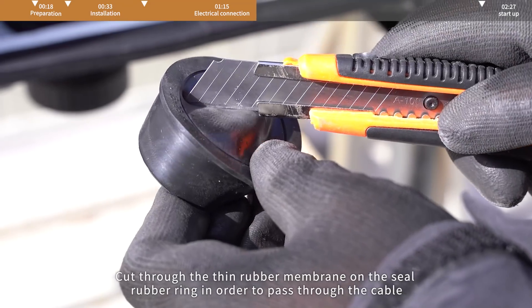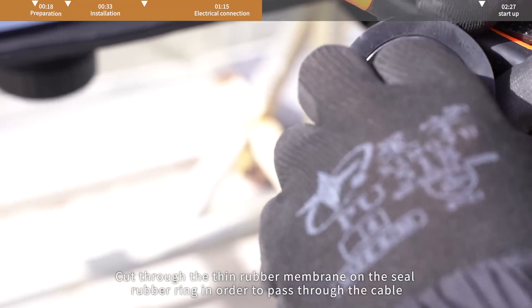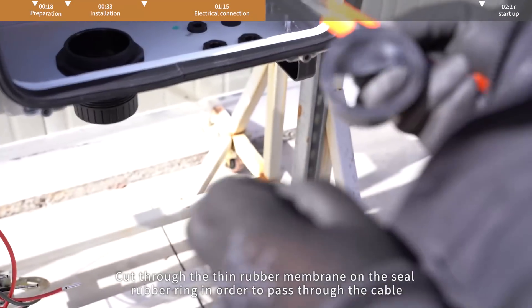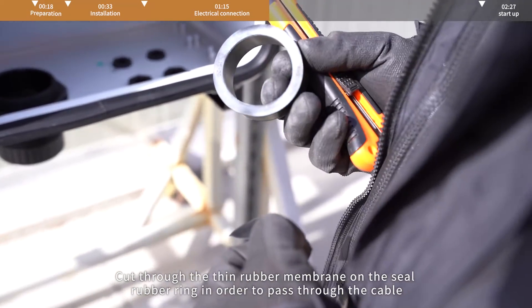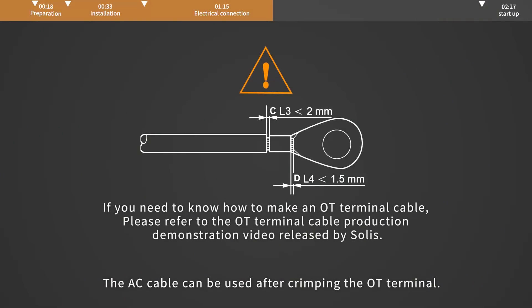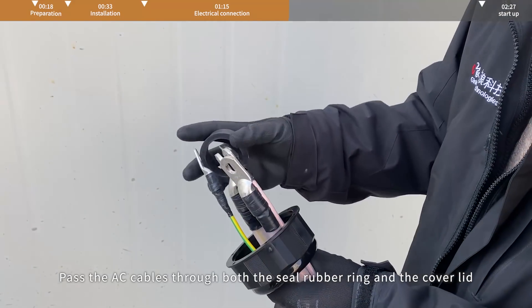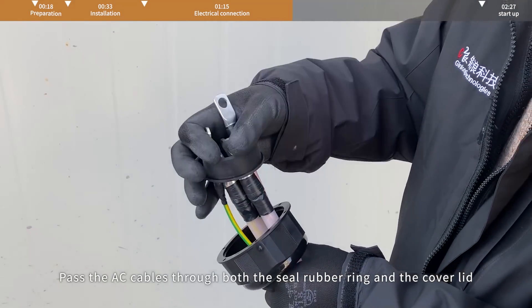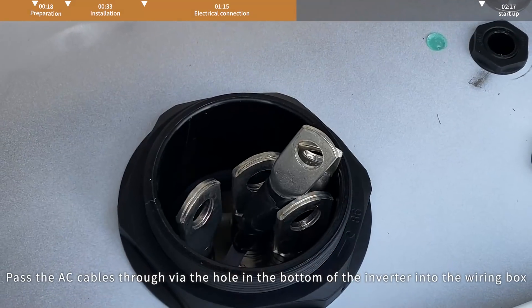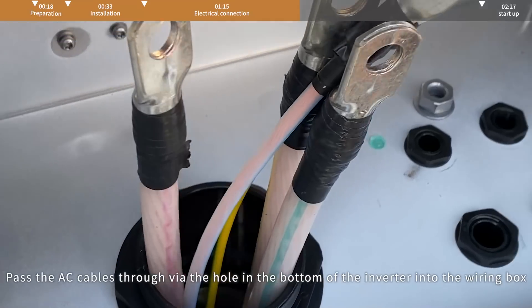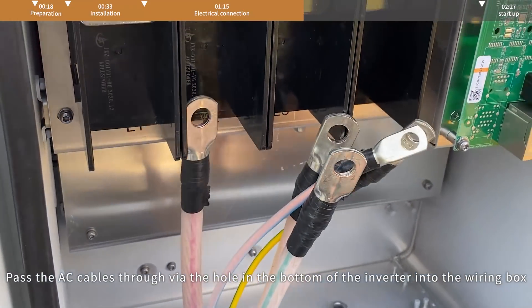Cut through the thin rubber membrane on the seal rubber ring in order to pass through the cable. The AC cable can be used after crimping the OT terminal. Pass the AC cables through both the seal rubber ring and the cover lid, then through the hole in the bottom of the inverter into the wiring box.